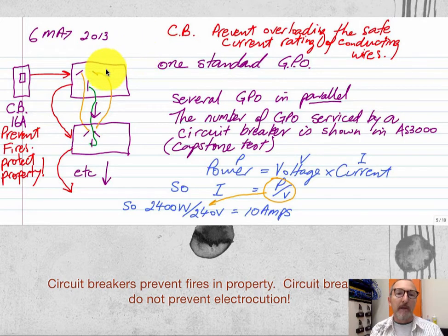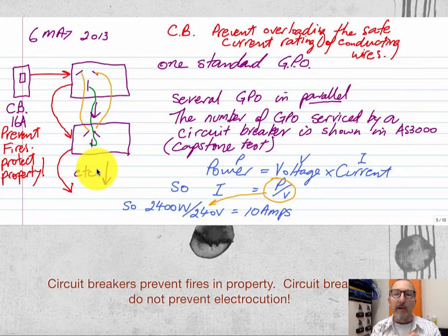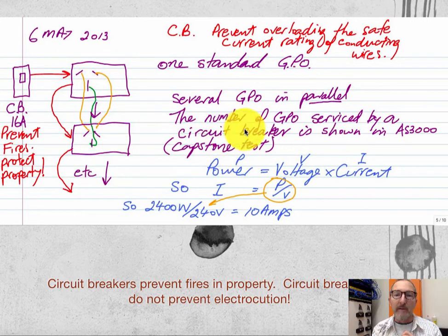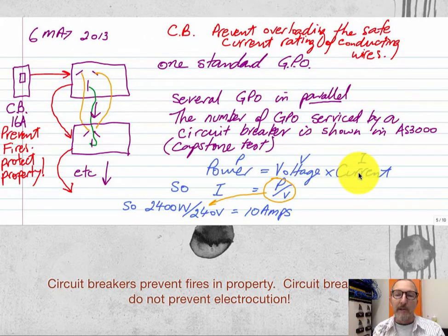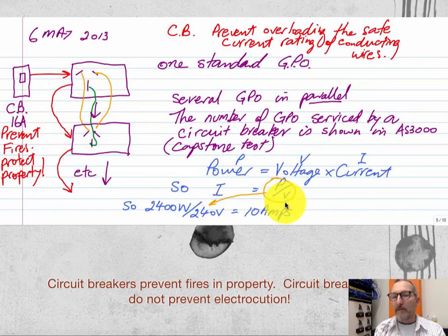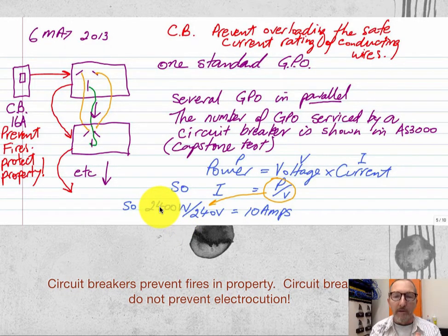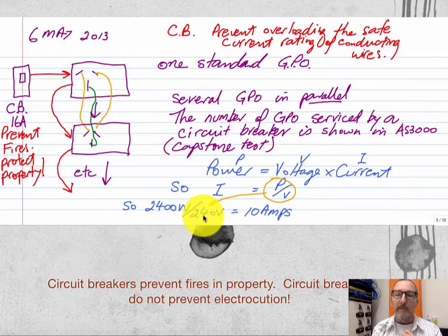Circuit breakers go to not one power point but normally more than one in a daisy-chain configuration — we might have several GPOs in parallel. The number of GPOs serviced by a circuit breaker can be found in the AS3000. Knowing a bit of maths: power in a circuit equals voltage times current, so current equals power divided by voltage. Earlier we had heaters at 2,400 watts with 240 volts supplying them — that's where the 10 amps came from.